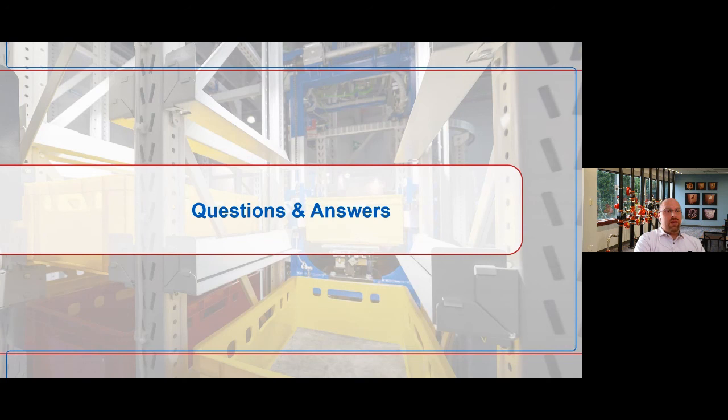I tend to feel that, and I'm not saying that I'm an expert on that, the presence of the longitudinal flue is a good thing. And I think what we're seeing with the automated storage, with the conveyors and the pallets, is that these pallets are butting up against each other, taking away that flue space. So potentially having the flue space, I think, is probably going to be acceptable, assuming that you use the sprinkler spacing that's prescribed as if it wasn't there. Yeah, and so I would also add a little bit to this.